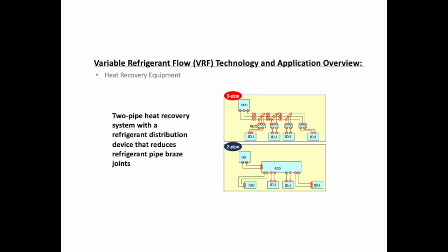Now, the advantage of a 2-pipe heat recovery system over a 3-pipe heat recovery system is that there's less labor to install these, typically less labor to install these systems. With a 2-pipe heat recovery system, you inherently have less piping and less brazing to do than on a 3-pipe heat recovery system. You can see that there's less connections to braze on a 2-pipe heat recovery system versus a 3-pipe heat recovery system. Less connection points means less labor, which means the contractor can get in and out of the job faster, and there's less labor to charge the owner with a 2-pipe system versus a 3-pipe system.